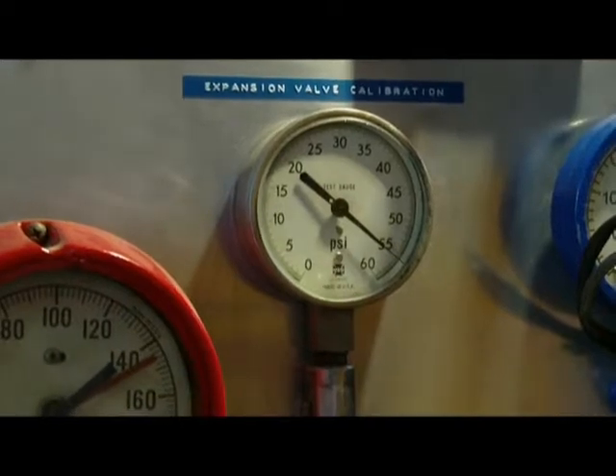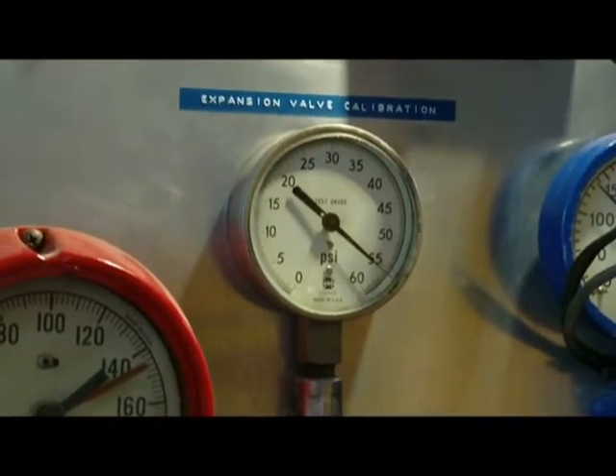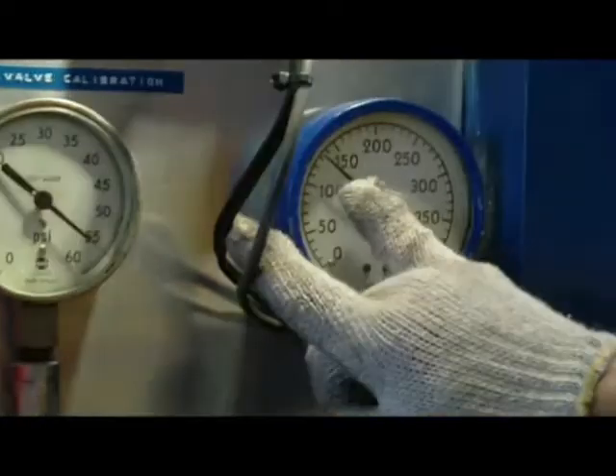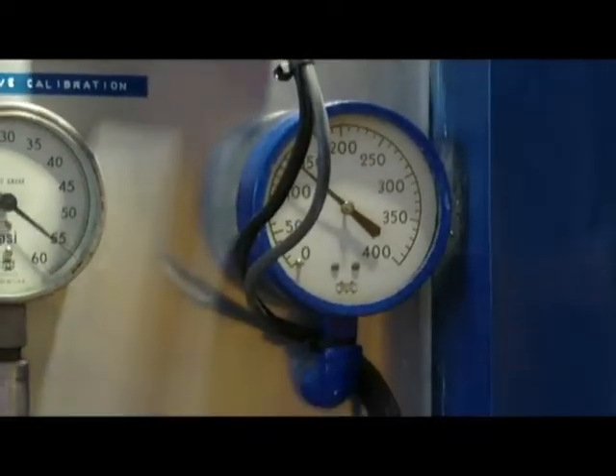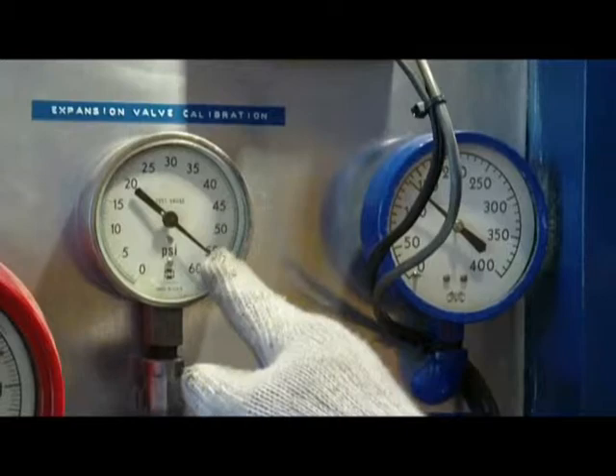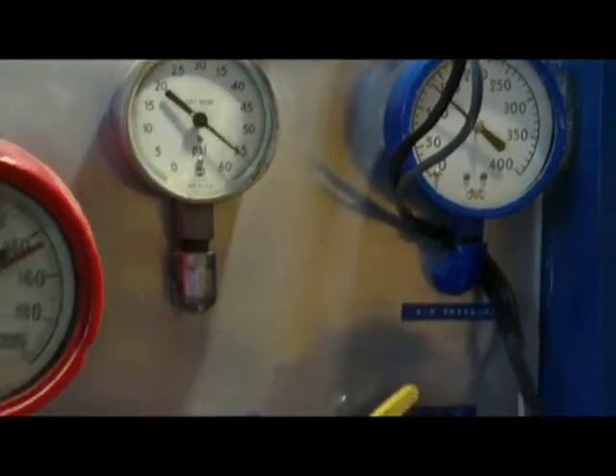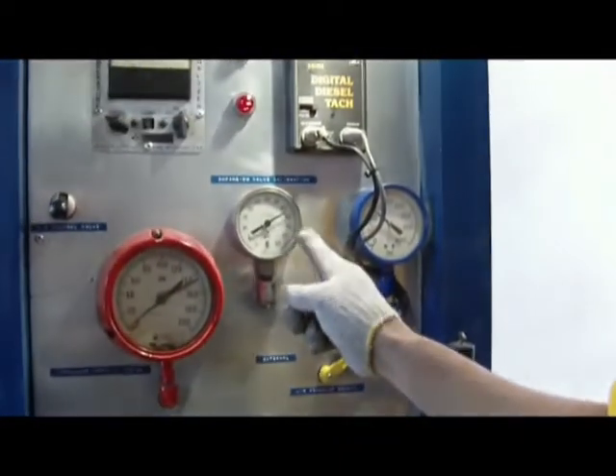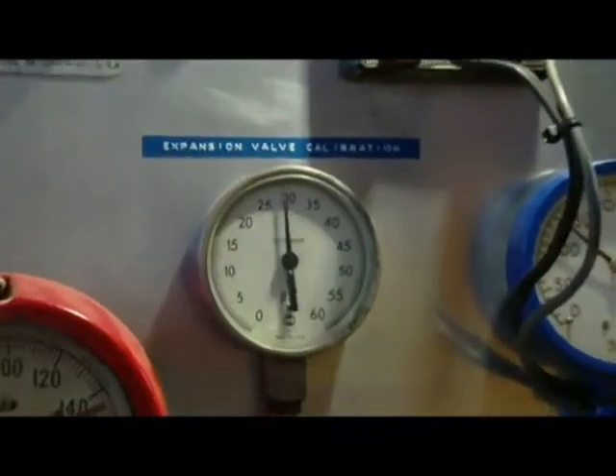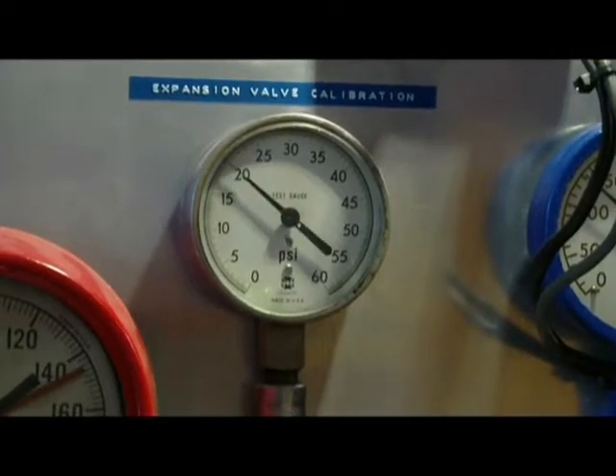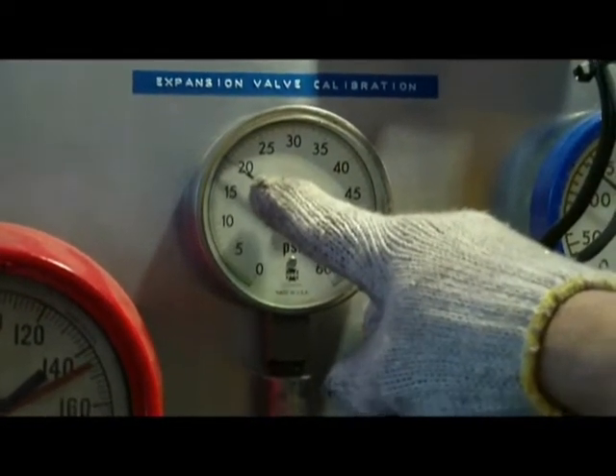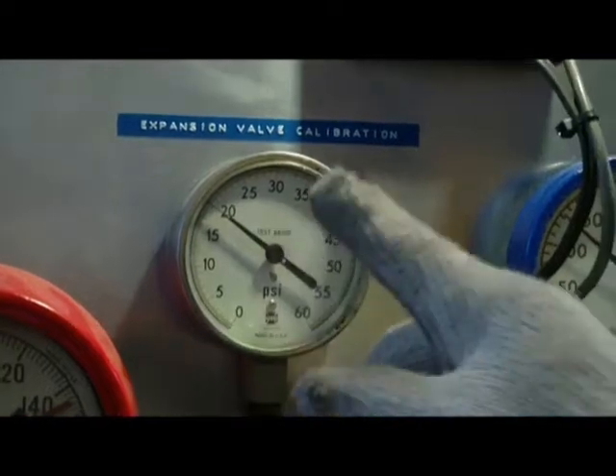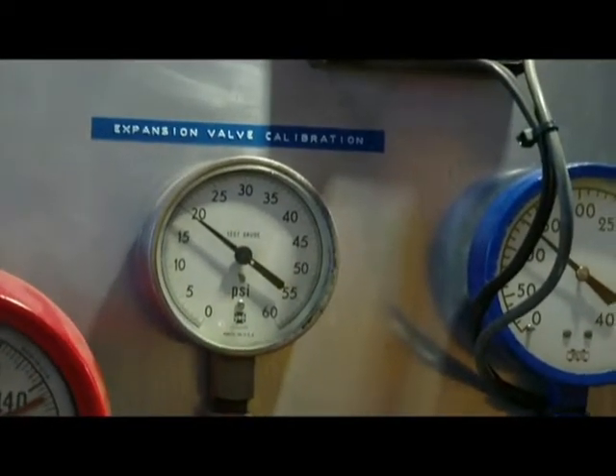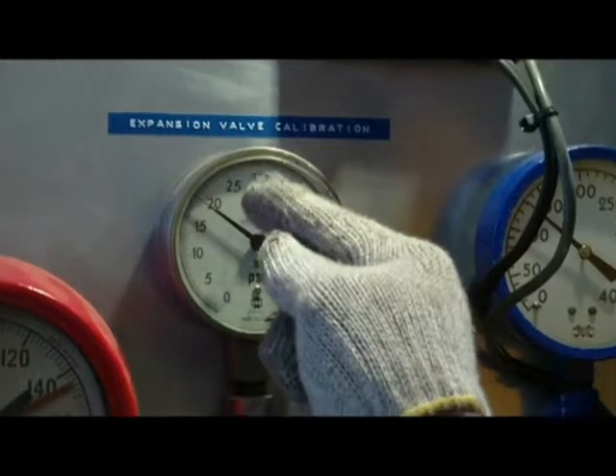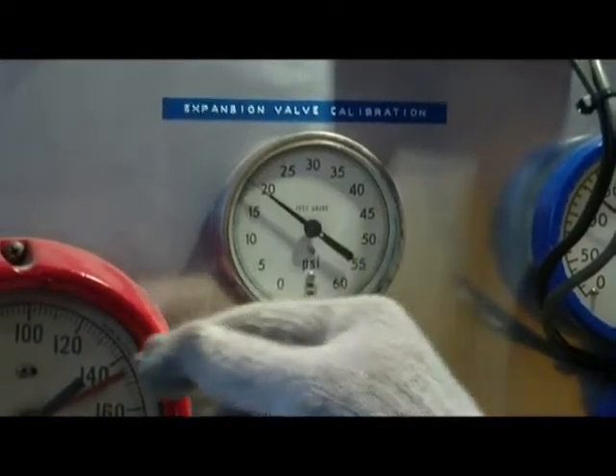So what we need to do is to put a cold ice here while the pressure is at 130 psi, so you can see the reading of the expansion valve here on this gauge. Okay, you will see it will go down once the capillary tube here gets cold. See, it's around 19. It's good already, but I will just show to you how to adjust an expansion valve. For example, it was very high or it's very low in reading.